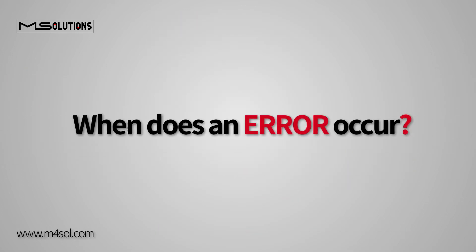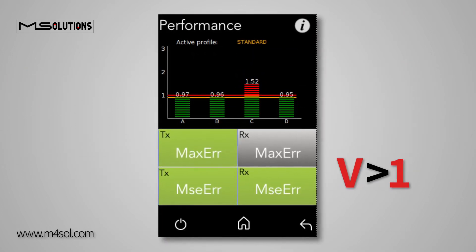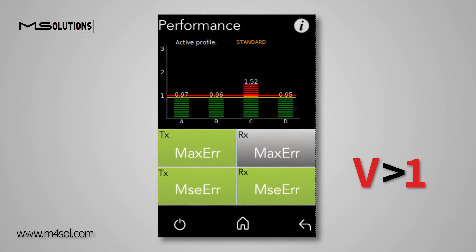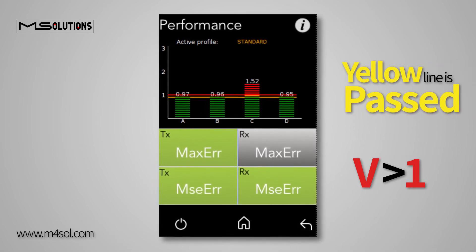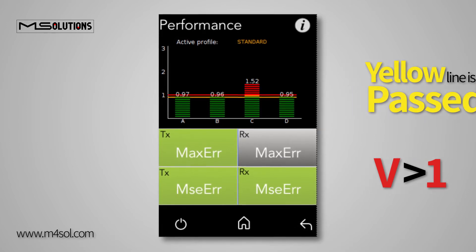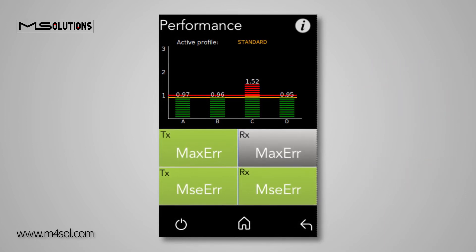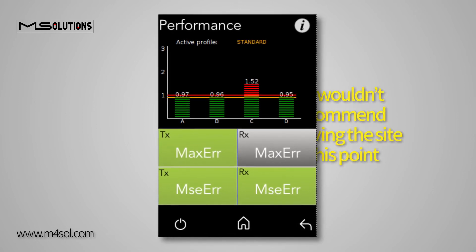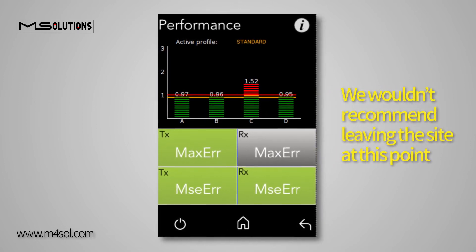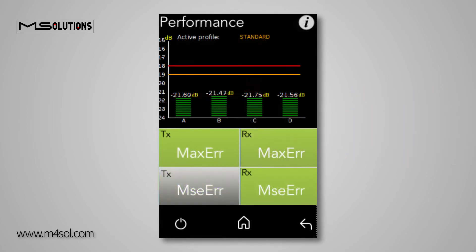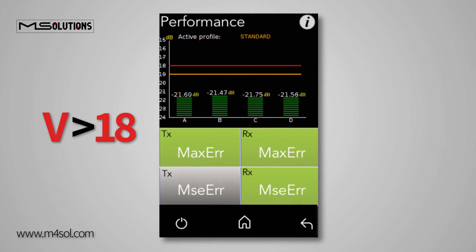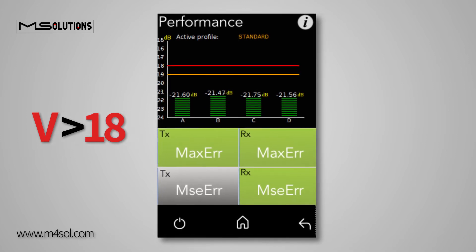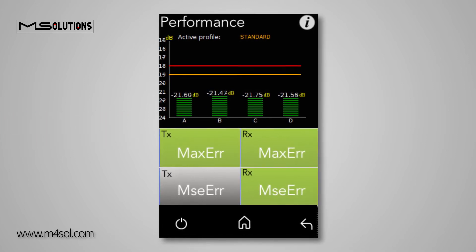When does an error occur? On the Receive side, when the value displayed is greater than 1, or when the yellow line is passed, an error condition is close at hand. If the measurements pass the red line, it's a sign that a critical malfunction exists that requires handling. We wouldn't recommend leaving the site at this point. On the transmitting side, measurements over 18 indicate a malfunction. As with the receiving side, a good cable installation won't reach the red line.